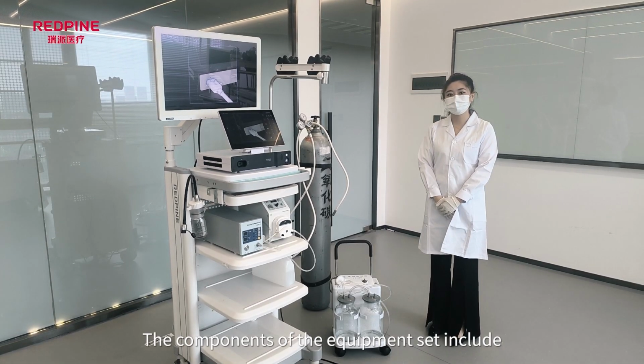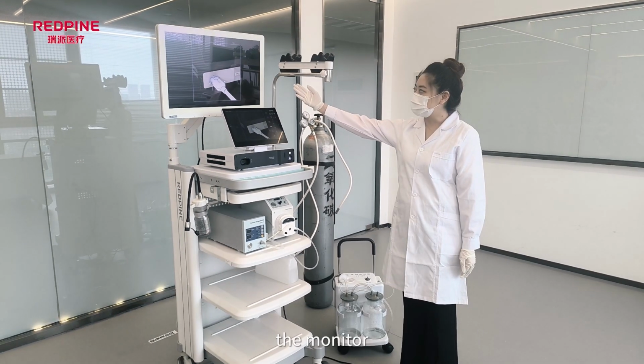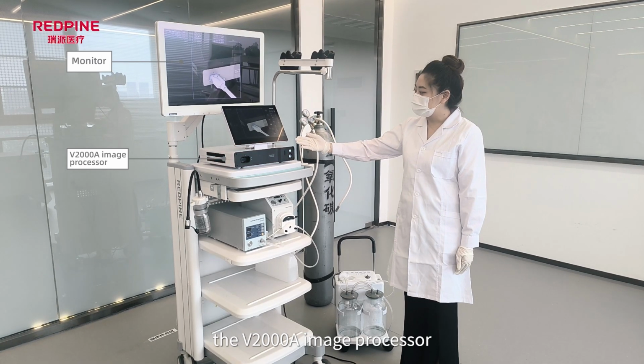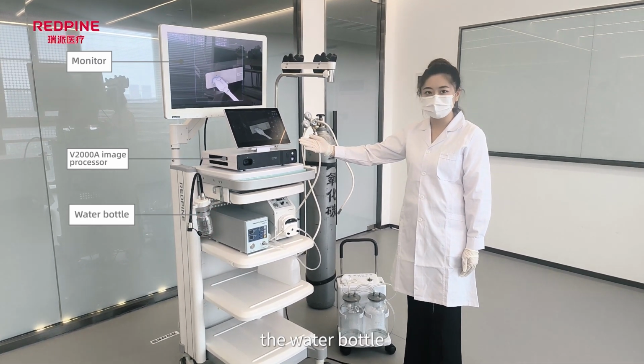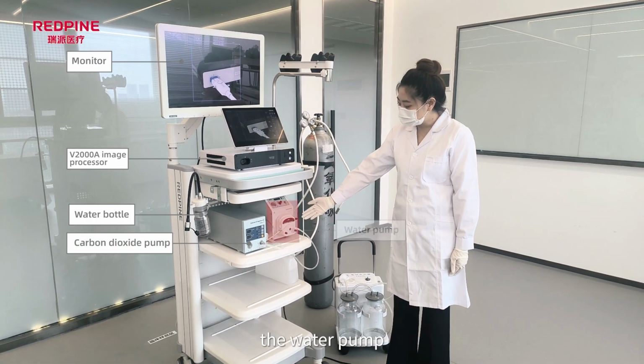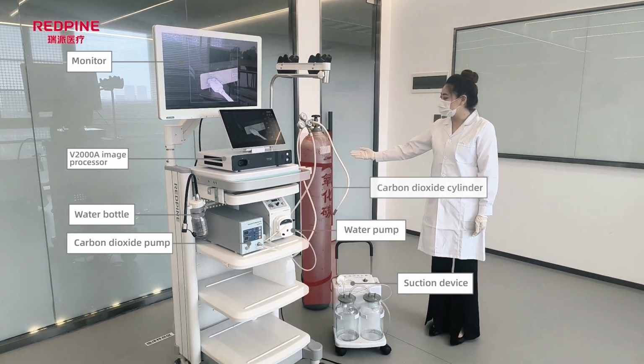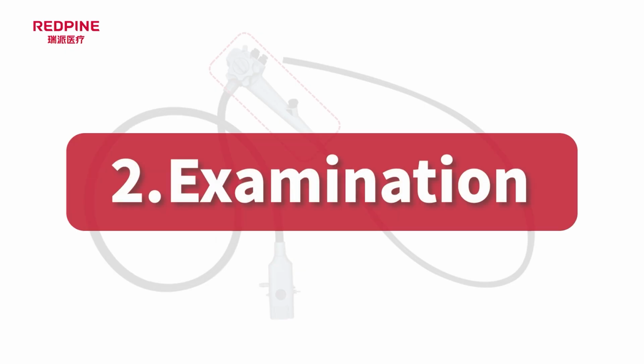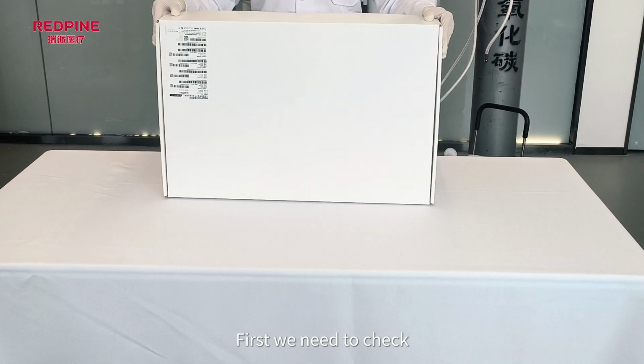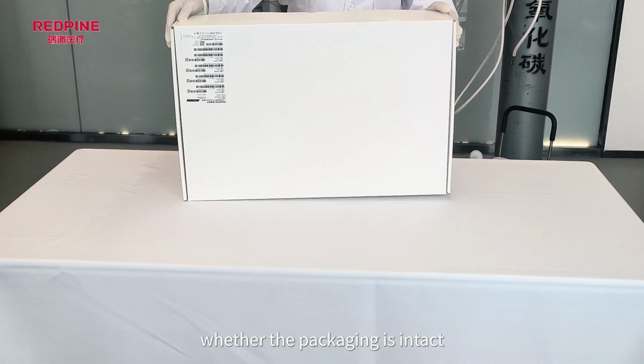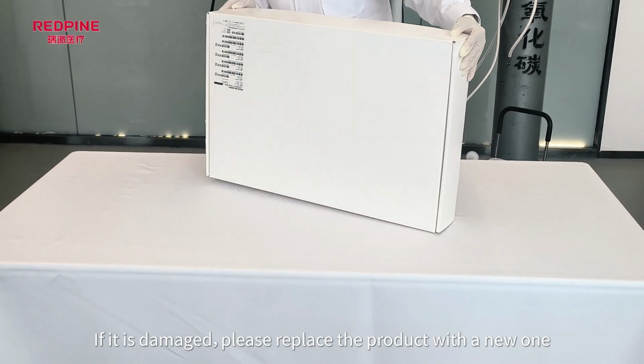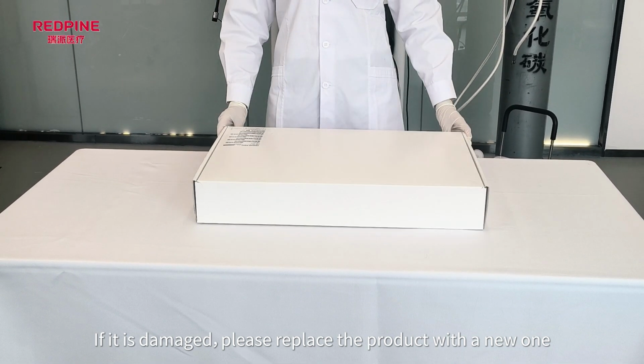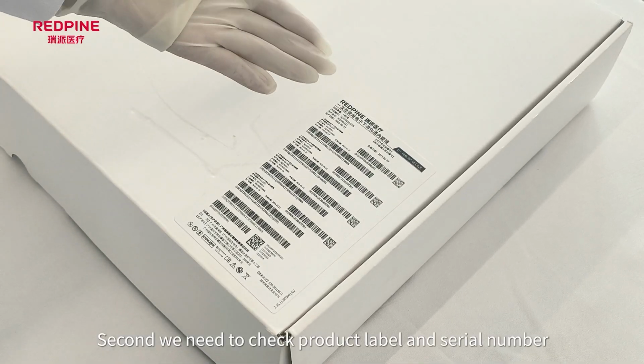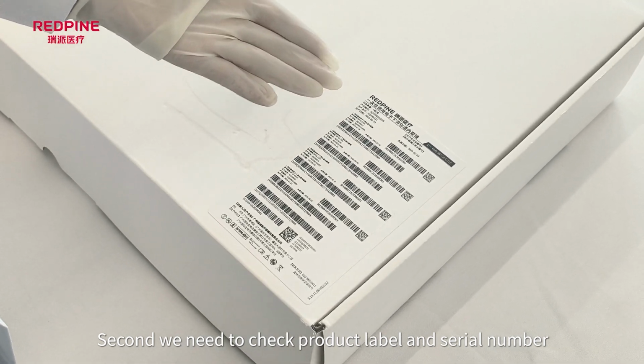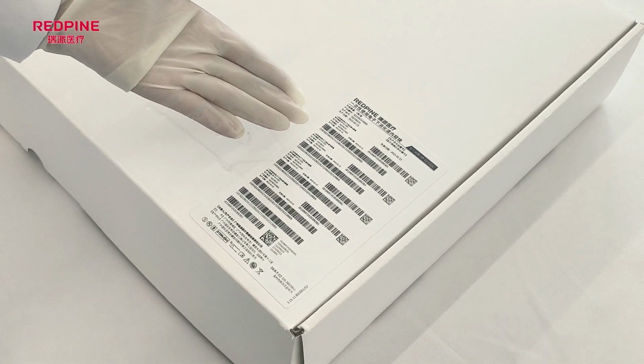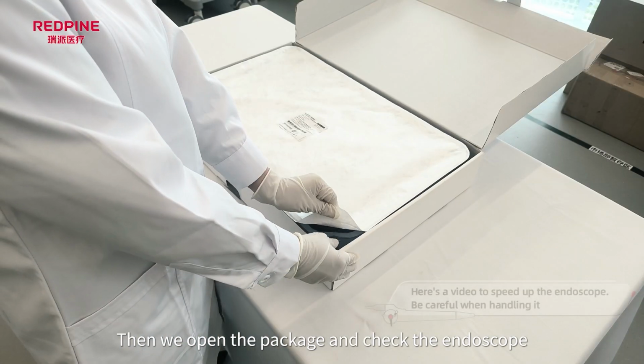The components of the equipment set include the monitor, the V2000A image processor, the water bottle, the CO2 pump, the water pump, the suction device and the CO2 cylinder. 2. Examination. First, we need to check whether the packaging is intact. If it is damaged, please replace the product with a new one. Second, we need to check product label and serial number. Then we open the package and check the endoscope.